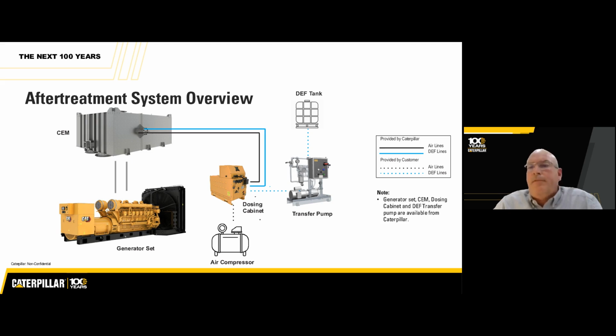We also have a DEF tank shown, more of a tote style. In an enclosure, you may have the DEF tank in the base of the enclosure, or one large DEF tank feeding multiple dosing systems. Usually in data center applications, because of redundancy, we see many customers having all these systems redundant for each engine, but we've also seen situations where one air compressor feeds two different SCR systems, or one tank feeds multiple dosing systems. So really it's up to how you're engineering your site, and it's one of the key considerations you need to take into account when designing your overall site.